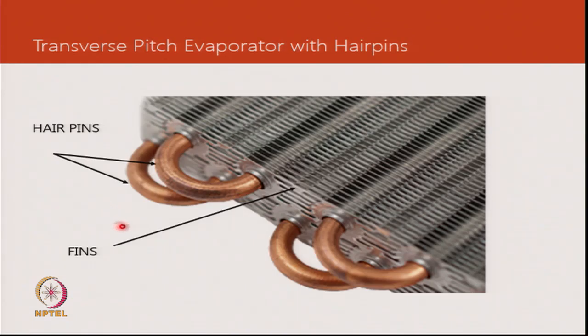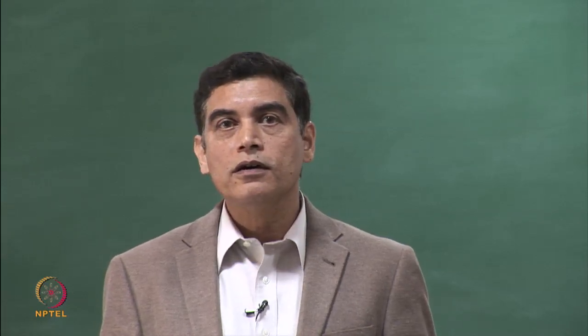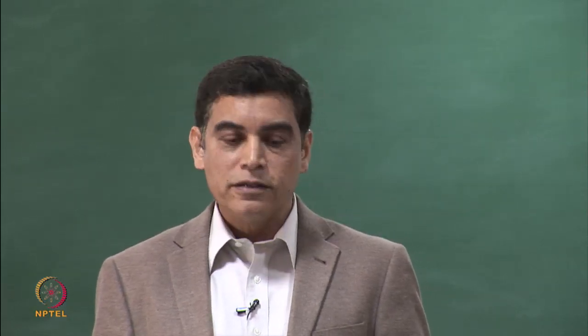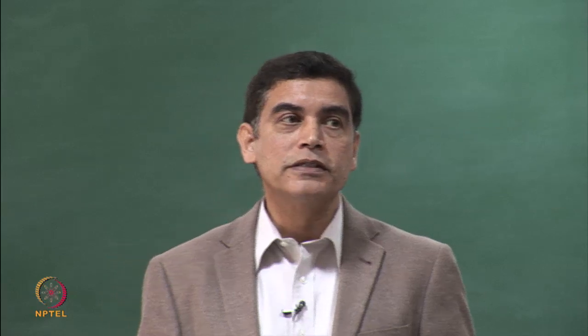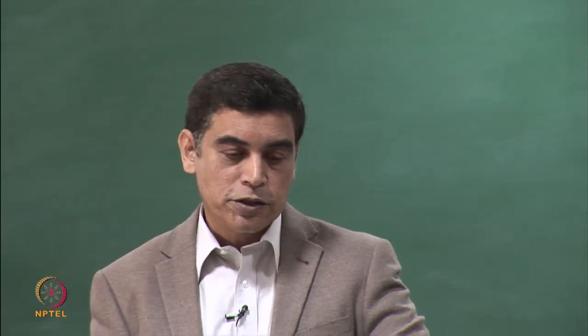The hairpins can be slid into the fins without great initial contact. An expansion process follows — either hydraulic or using a bullet expander. Most coil manufacturers today use bullet expansion, where an expander travels the entire length of the tube to firmly bond it to the aluminium fins, also adding structural strength to the heat exchanger.